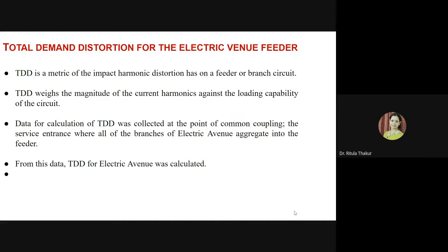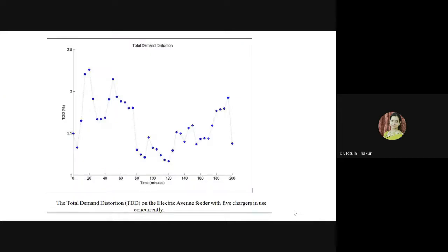So in order to calculate the TDD, the data was collected at the point of common coupling. This common coupling was actually a service entrance where all the branches of Electric Avenue aggregated into the feeder. And from this data, the TDD for Electric Avenue was calculated. And this is the figure, as you can see from here. This is the total demand distortion on the Electric Avenue feeder, in which 5 chargers were concurrently in use. Ideally, it happens rarely that all the 5 chargers are simultaneously used.